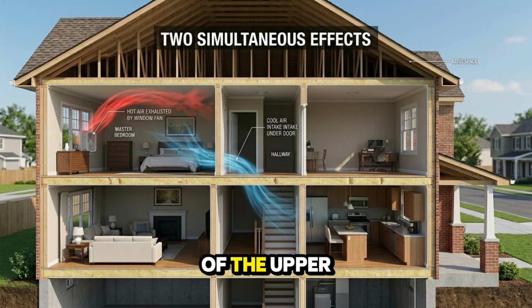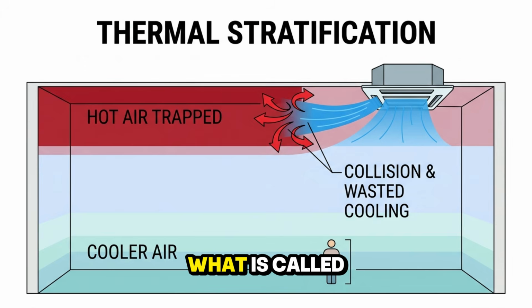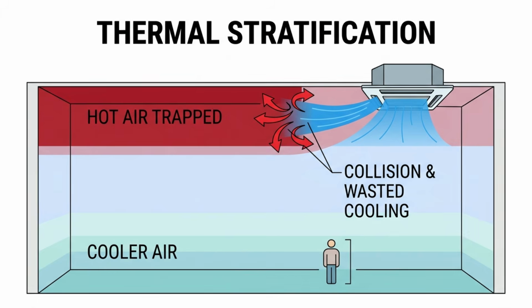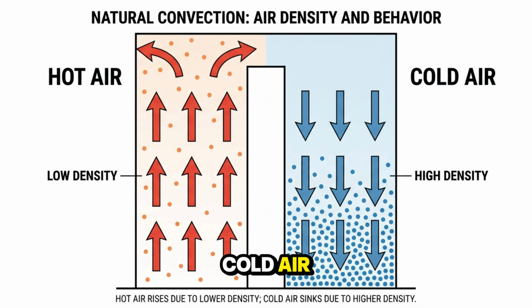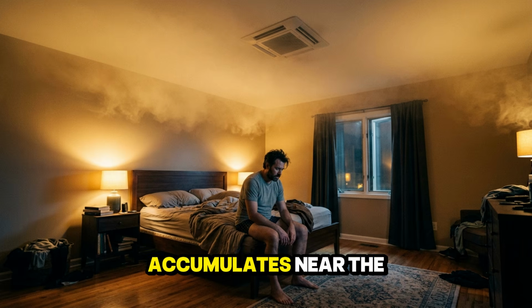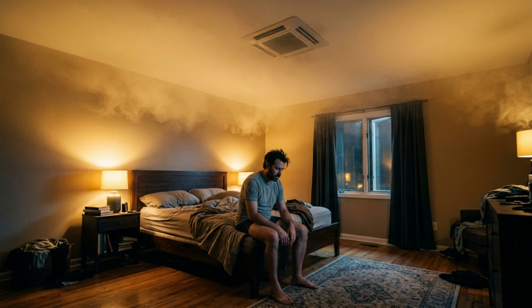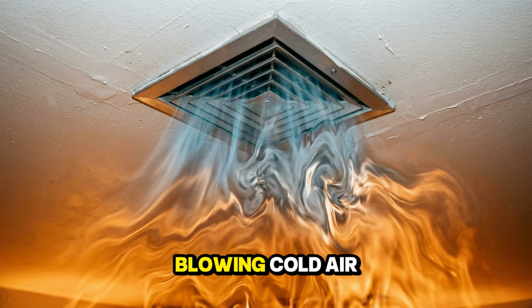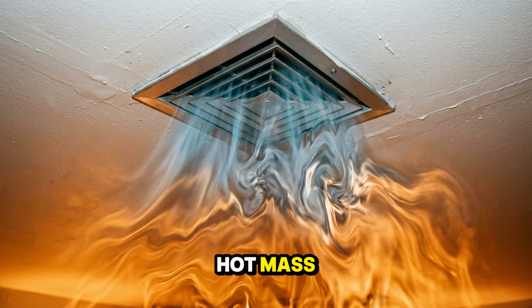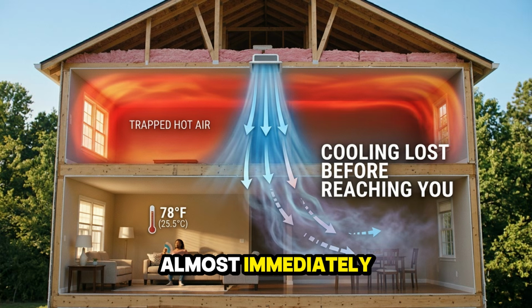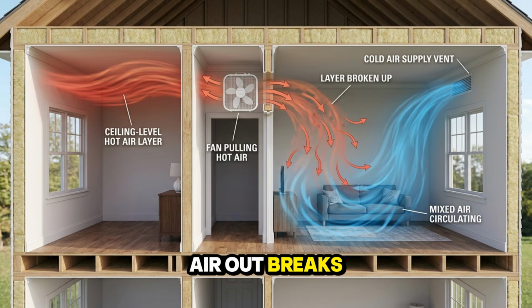When you pull hot air out of the upper part of the room, two things happen simultaneously. First, you disrupt what is called thermal stratification. Hot air is less dense than cold air. In a sealed room, the hottest air accumulates near the ceiling in a thick, stagnant layer. Your ceiling vent is blowing cold air directly into that hot mass, and it loses its cooling power almost immediately. You're fighting the ceiling the entire time. Pulling that hot air out breaks up the layer. The room starts mixing properly.